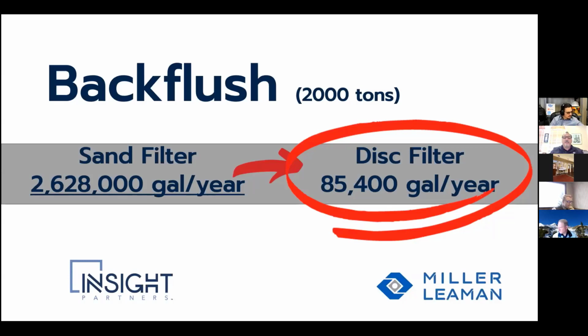So again, if you're using city water, then you're just blowing all that city water down the drain. If you're using tower water, that 2 million and 85,000 is going to contain chemicals, which then you're wasting. You also won't keep the chemicals balanced in a cooling tower with a sand filter that backflushes, because it's such a large amount of water. You blow down those chemicals, then your chemical charts go nuts, and they need to inject the chemicals in to keep it balanced, where the disc filter doesn't have that effect on the chemicals on a cooling tower.